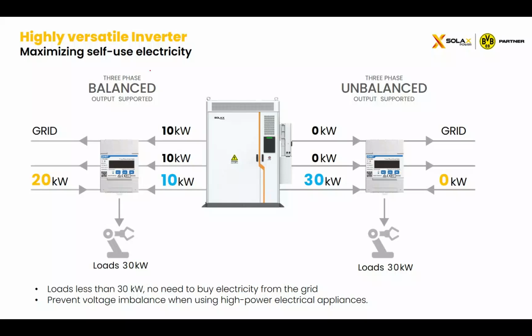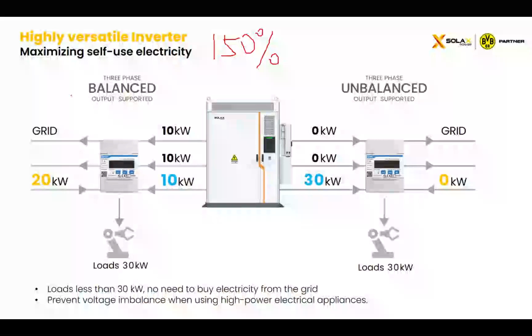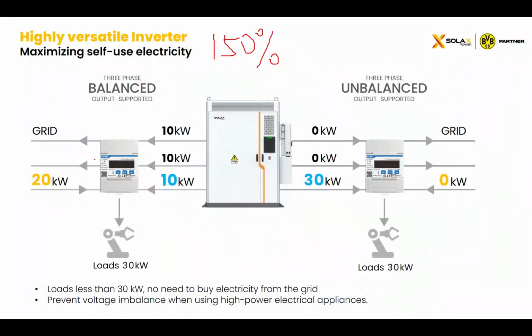Okay, and the next is about the three-phase unbalanced output. The AELIO has the ability of 150% three-phase unbalanced output. That means if an inverter does not have this function, and someone connects single-phase loads to any phase of it, and the load needs 30 kilowatts, even if the inverter can produce 30 kilowatts of energy, each phase can only output 10 kilowatts. So for this kind of inverter, they have no choice but to buy another 20 kilowatts from the grid, and that will cost some money.